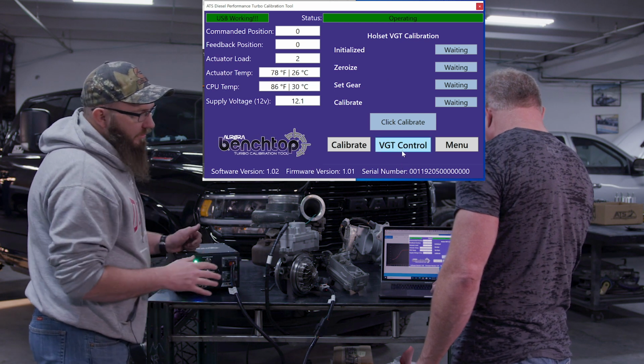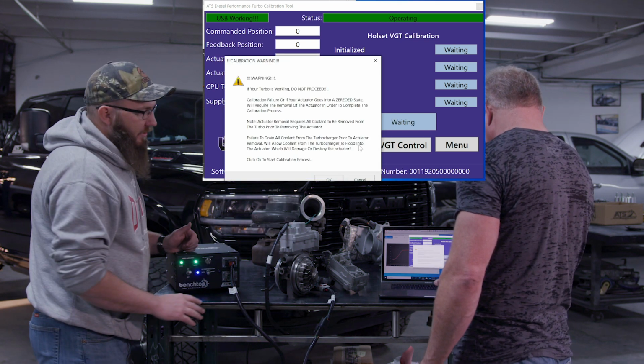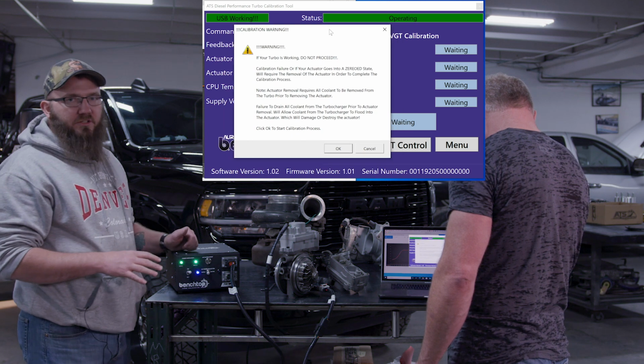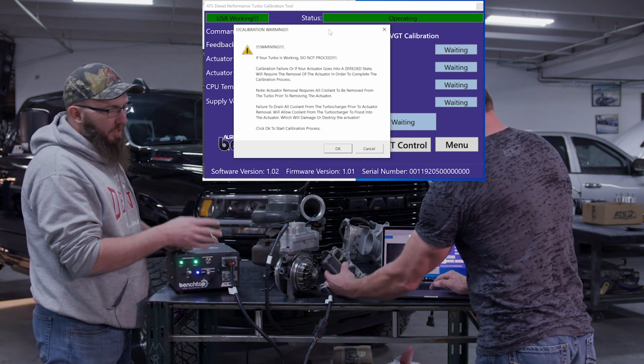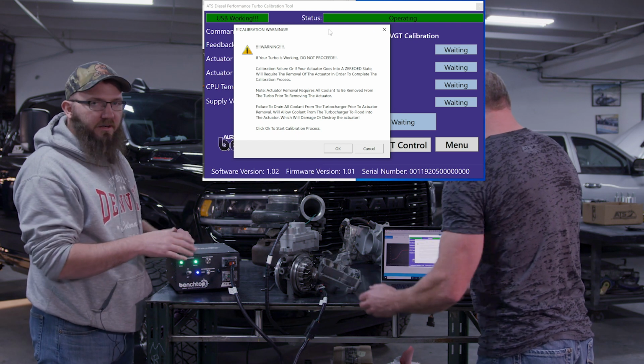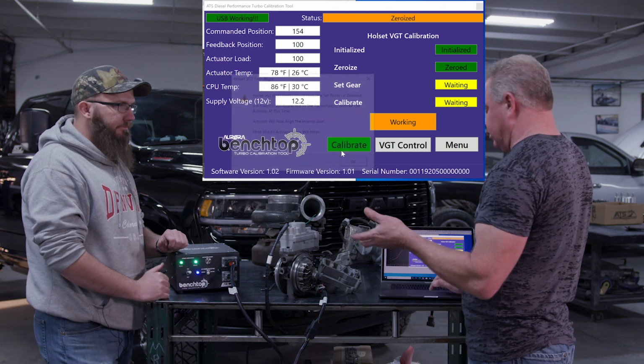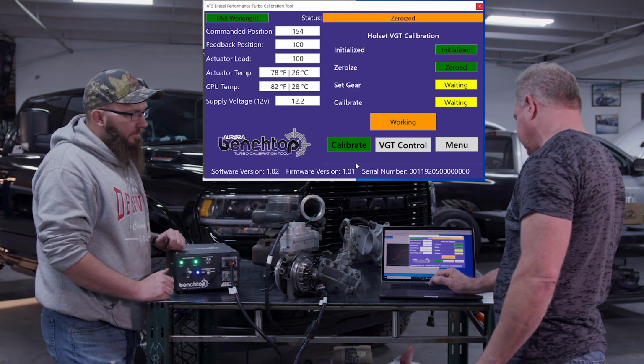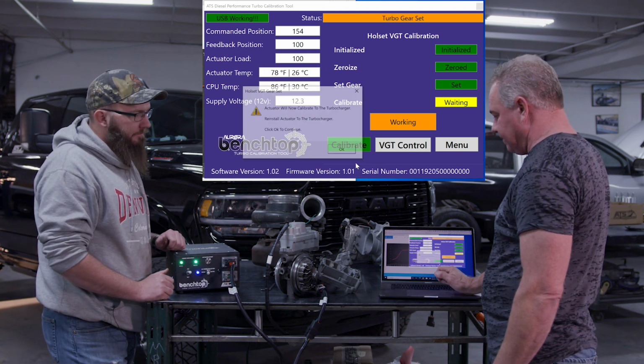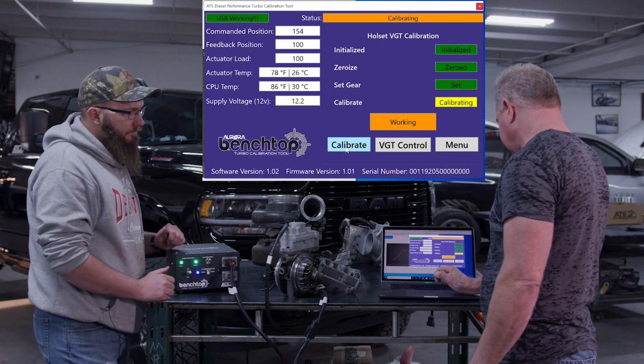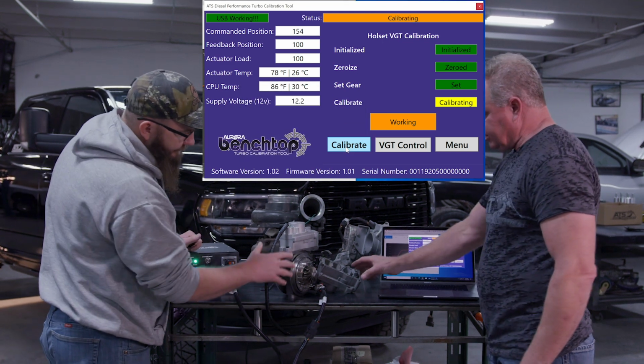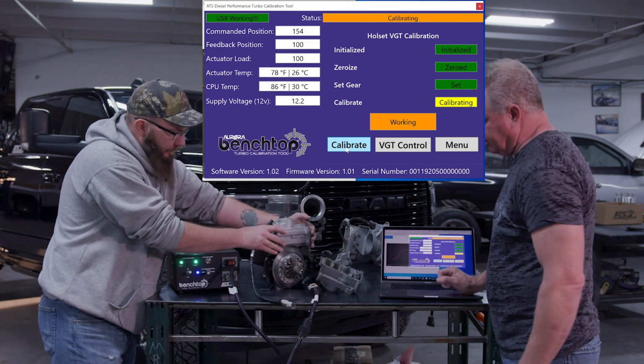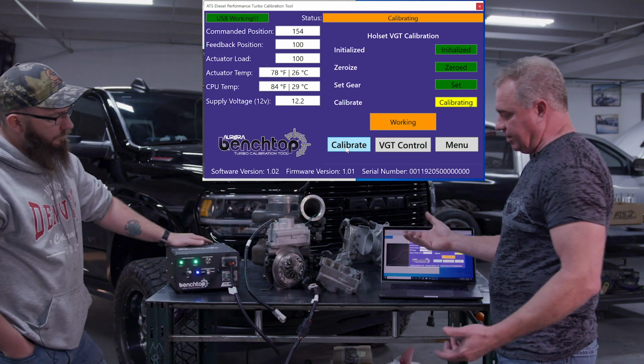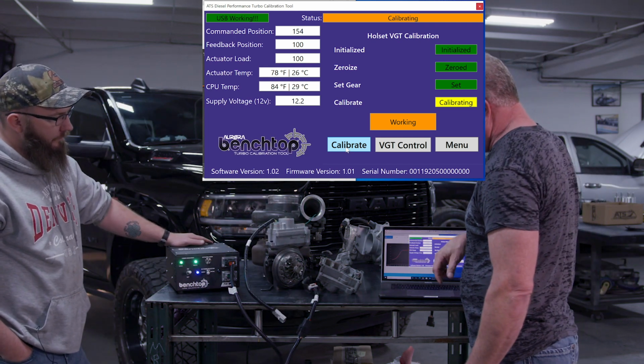So the whole point we're trying to do now, click calibrate, is we're actually going to do a calibration without the center cartridge. And we're going to show you that if there's something going on during the calibration process, it will error out. All right, so we're going to just run through it. Now we're not going to bolt it to the turbo in this case. We're just going to go through the calibration without it. What it's doing now is trying to find its 0 to 100 set point, but it's not going to find it because it doesn't have vanes stopping it.